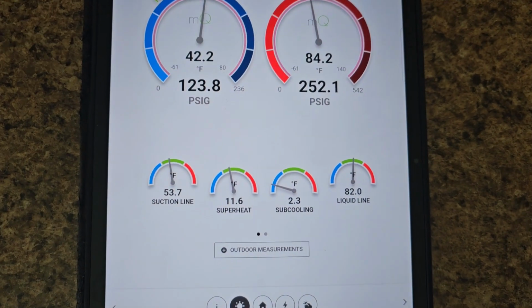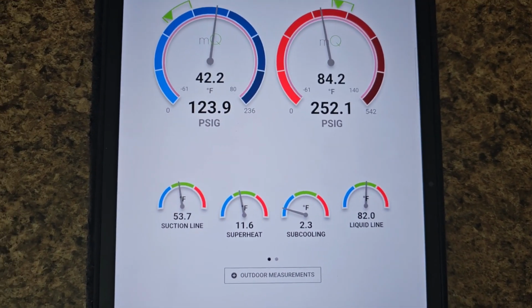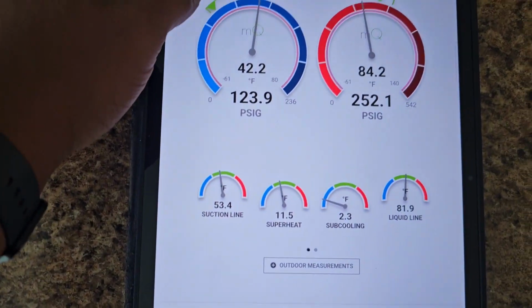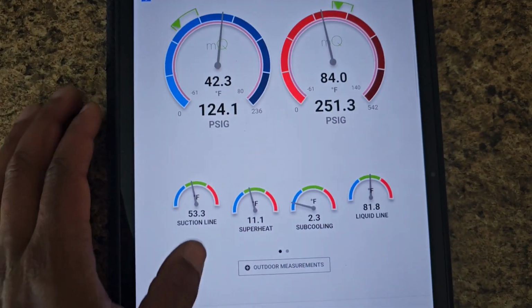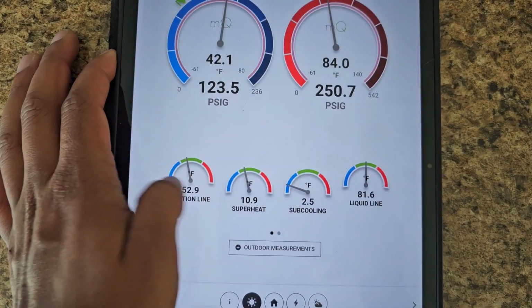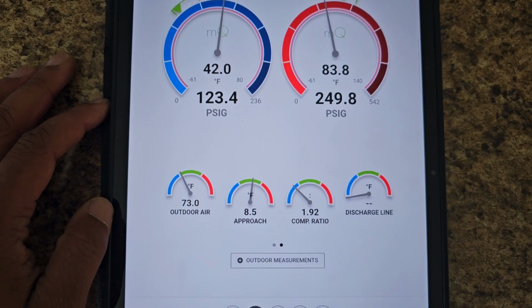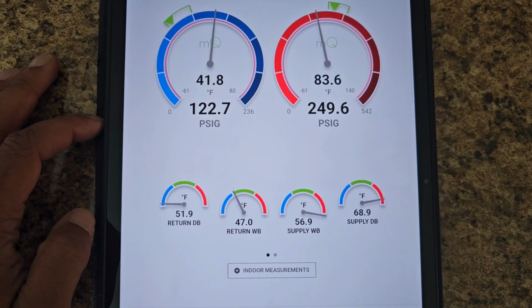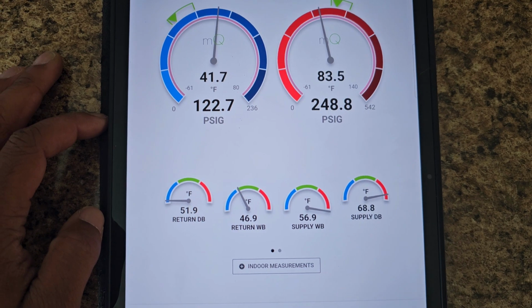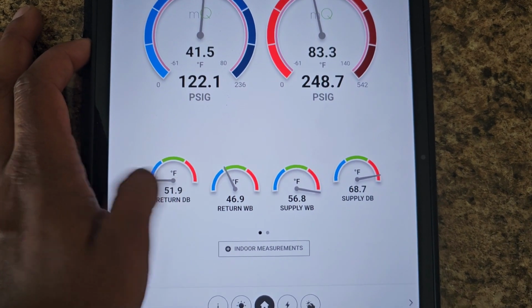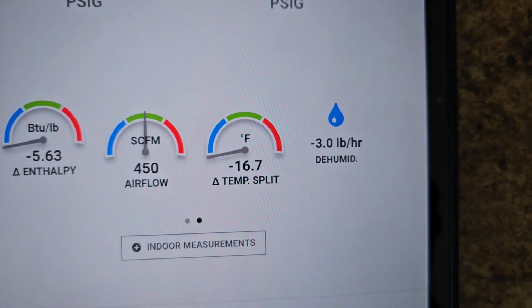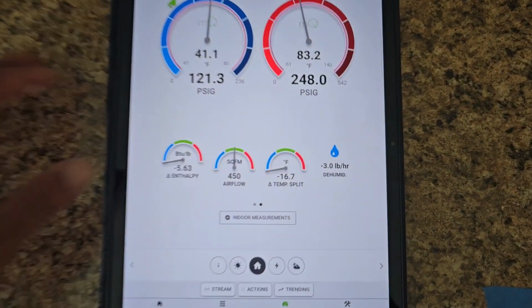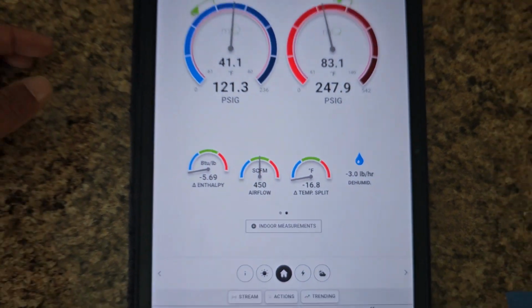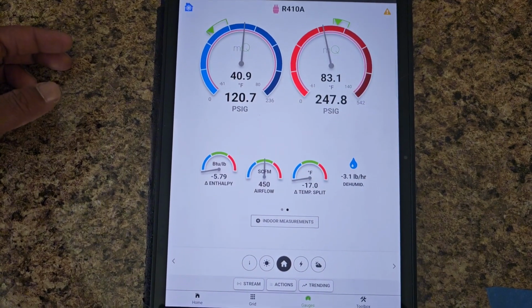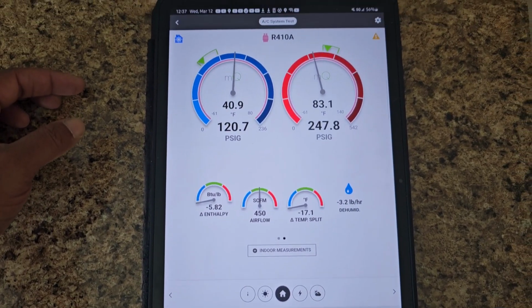There's really no load outside. It's not really that hot outside, and it's not really that hot inside. So given the outdoor and indoor measurements, this is what Measure Quick would want me to be at. But I feel like I'm outside of the range. But we're getting a pretty okay temp split for me personally. Given that there is no real load on the house right now, I feel like 16.8 degrees isn't that bad.